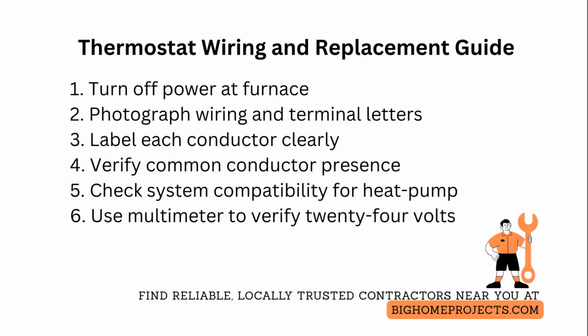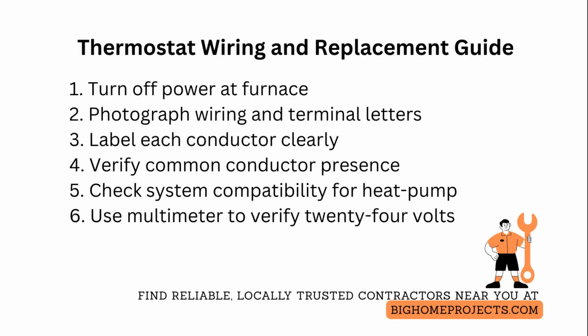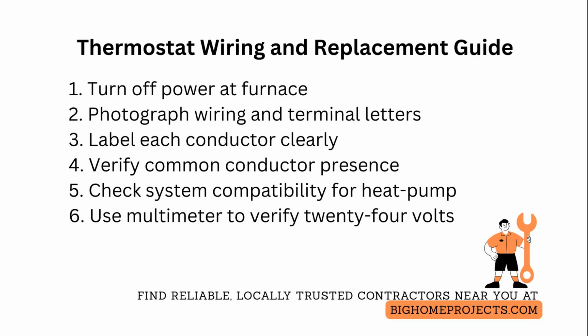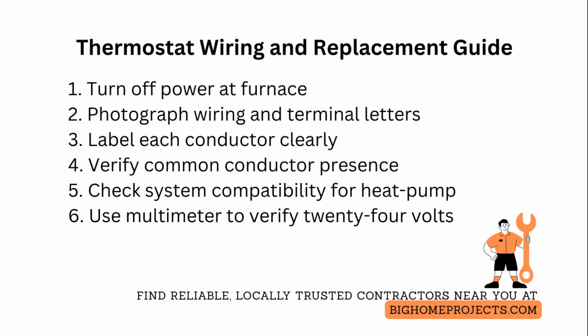If there is no common conductor, confirm the system's transformer output voltage and whether the new thermostat requires a continuous power feed. For heat pump systems or older millivolt and line voltage systems, check compatibility specifically. Heat pumps often use an O or B reversing valve wire that must be assigned exactly, and line voltage units cannot be driven by low voltage thermostats.